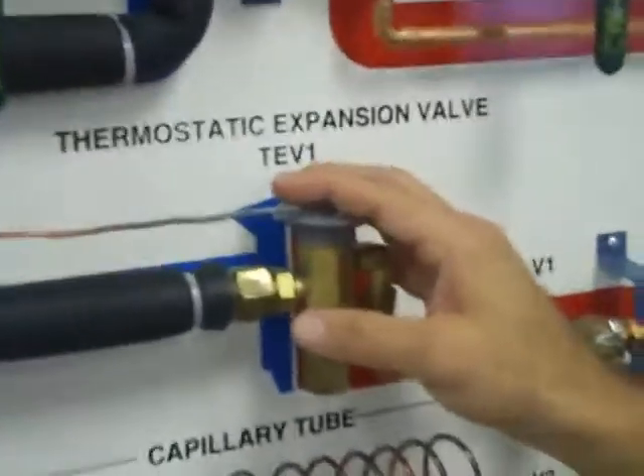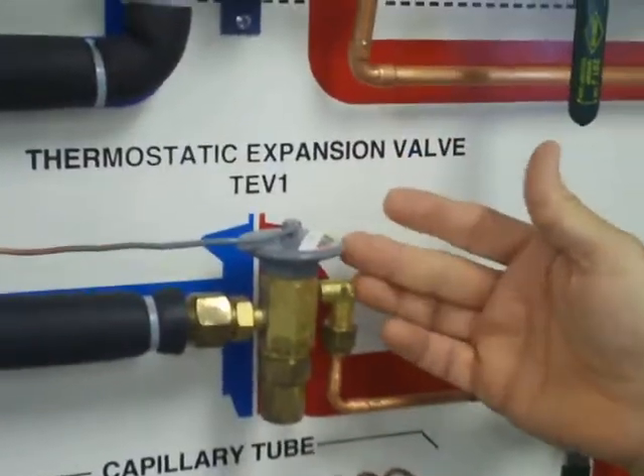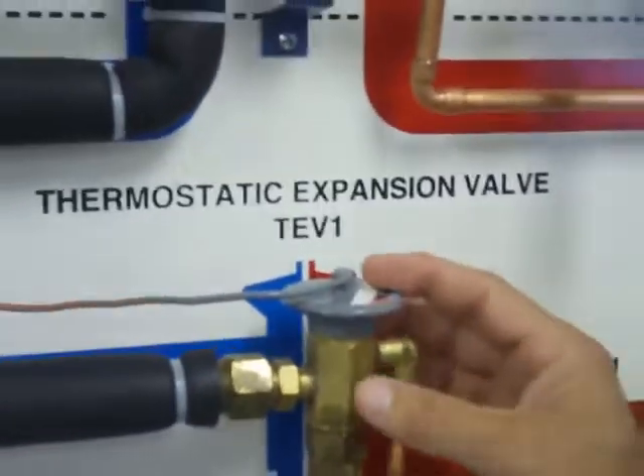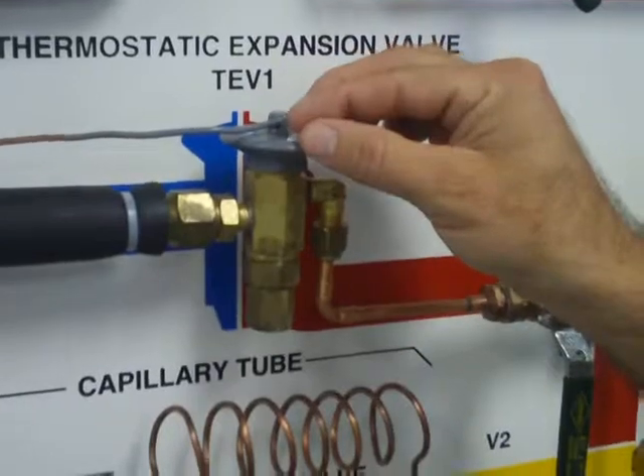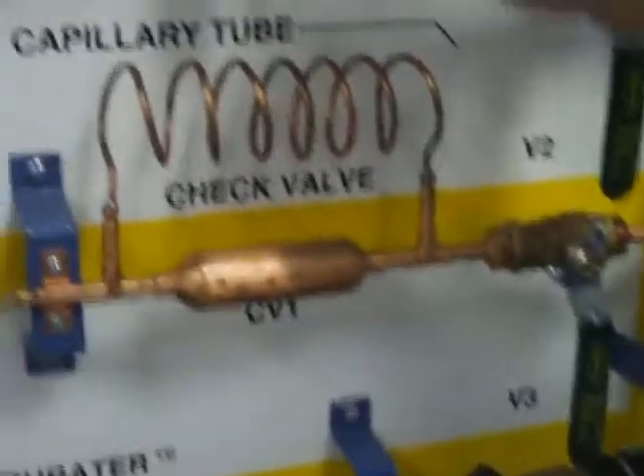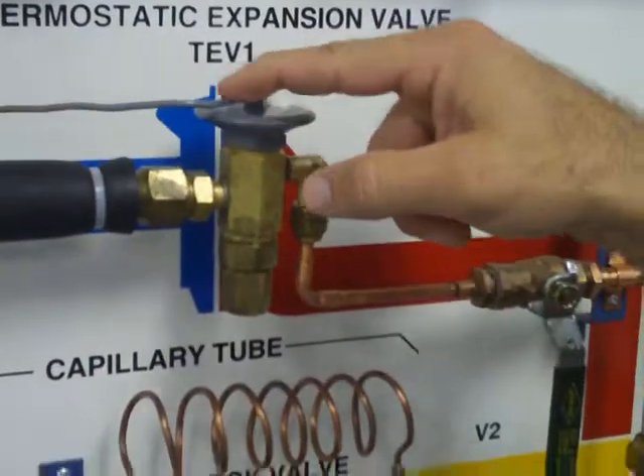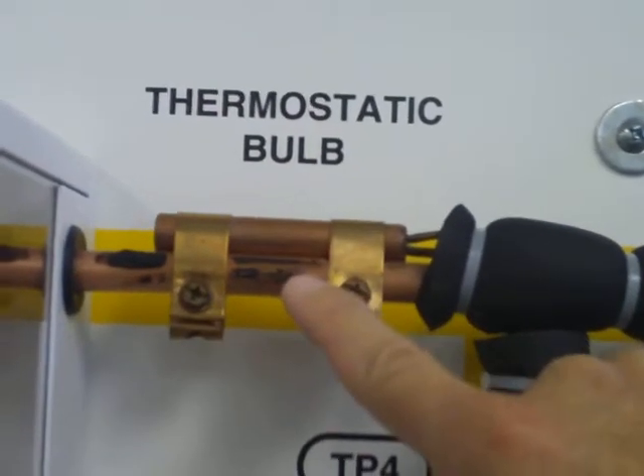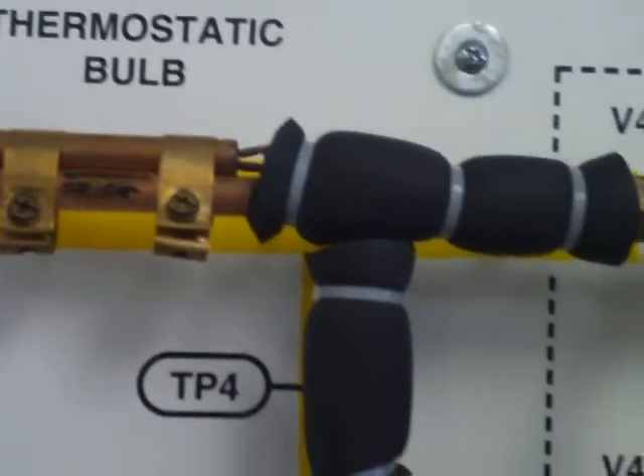The non-fixed or throttling type pressure reducing device is referred to as a thermostatic expansion valve, or TXV. What they consist of is a main valve body, spring, and head, and that's attached to the entering side of the evaporator, just as the fixed devices would be. But it monitors the temperature and pressure by a capillary tube and a sensing bulb that is attached on the leaving side of the evaporator.